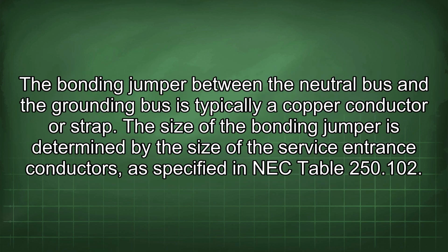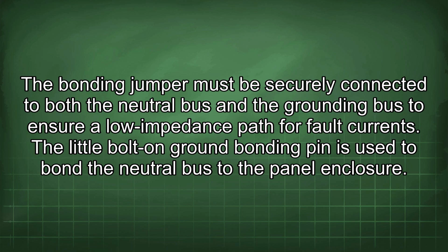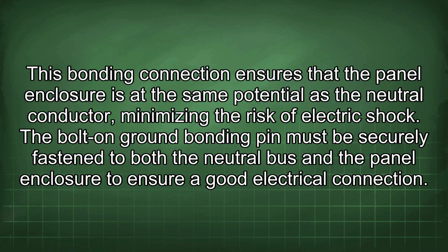The NEC provides guidelines for calculating the neutral load and determining the appropriate size of the neutral bus. The bonding jumper between the neutral bus and the grounding bus is typically a copper conductor or strap. The size of the bonding jumper is determined by the size of the service entrance conductors, as specified in NEC Table 250.102. The bonding jumper must be securely connected to both the neutral bus and the grounding bus to ensure a low impedance path for fault currents. The little bolt-on ground bonding pin is used to bond the neutral bus to the panel enclosure. This bonding connection ensures that the panel enclosure is at the same potential as the neutral conductor, minimizing the risk of electric shock. The bolt-on ground bonding pin must be securely fastened to both the neutral bus and the panel enclosure to ensure a good electrical connection.